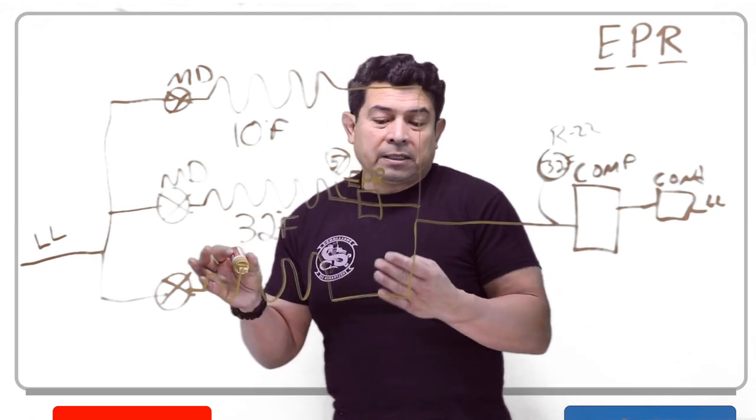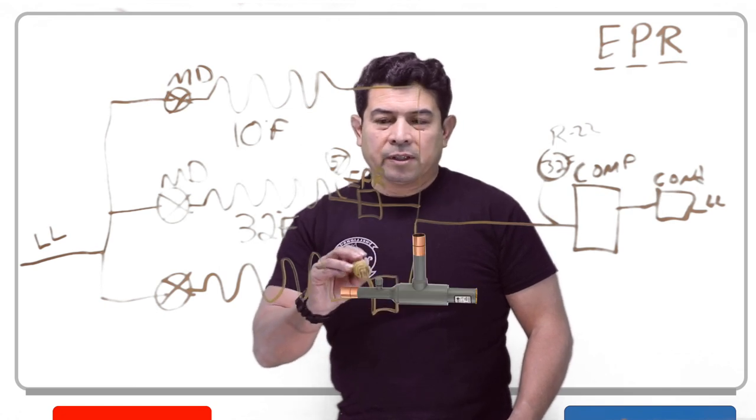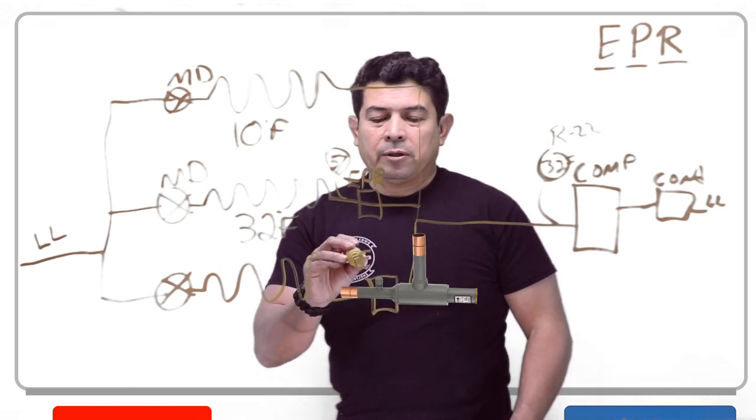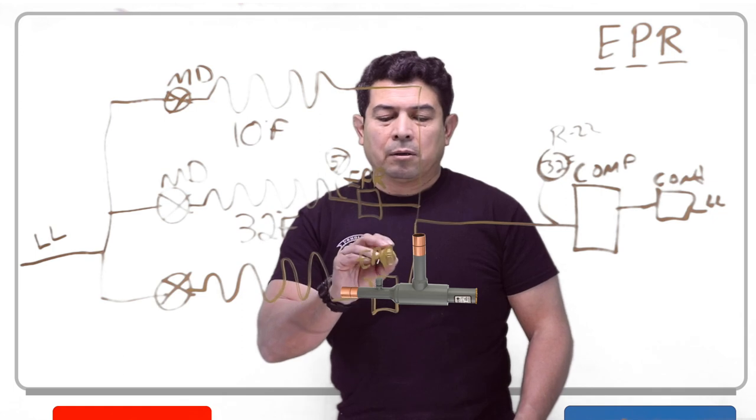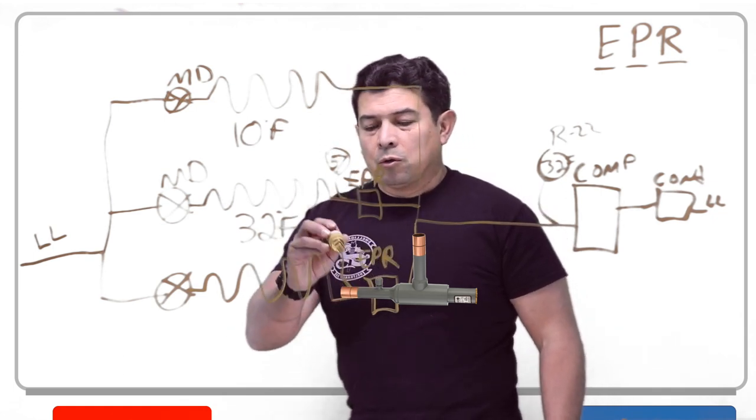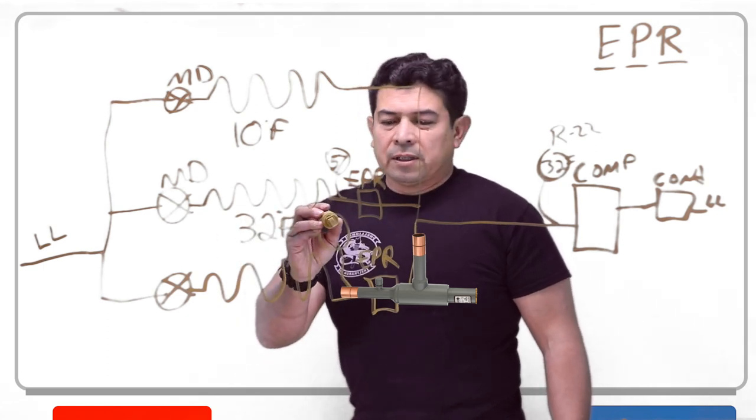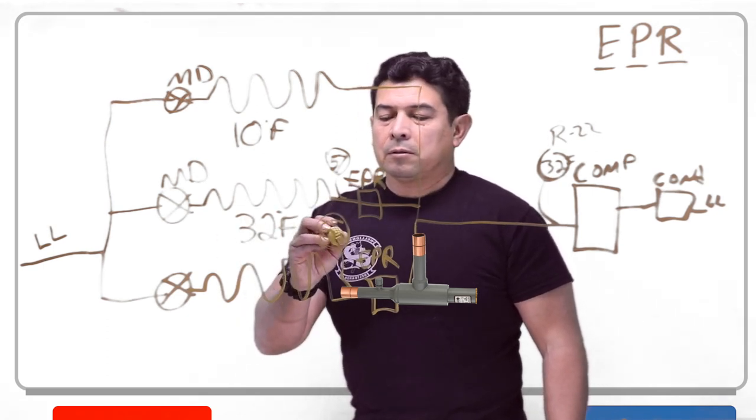But we don't want this - at least maybe we don't. In this example, we're going to put another EPR valve right there. Because we put another one, we're going to raise the pressure in this evaporator to, let's say, 68.